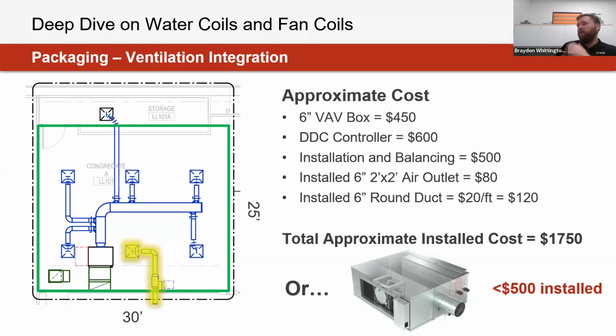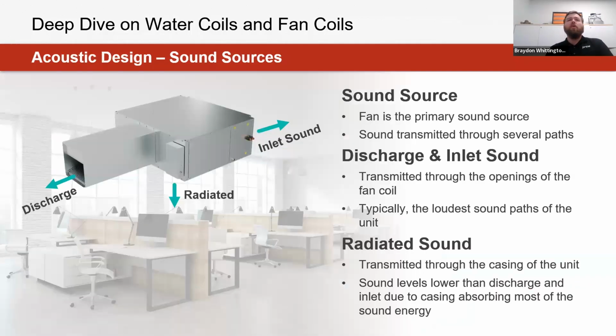So one consideration, especially when dealing with fan and blower coils, is instead adding that intake or fresh air intake onto the unit itself to be able to cut down on the additional cost that would be required for trying to add an individual VAV to our system there. And that's becoming, I would say, more and more popularized. That's a big word for me for these systems there too.